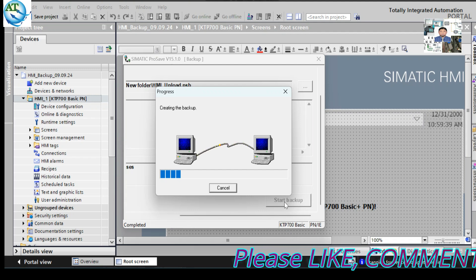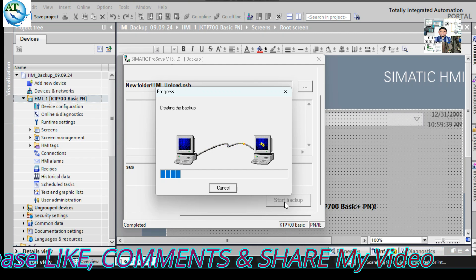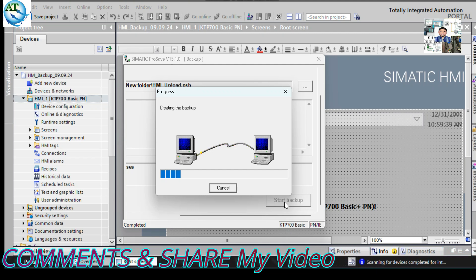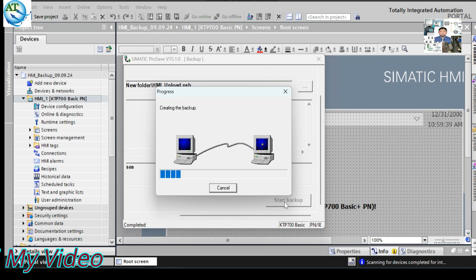In this video, I will show only the backup process. I cannot show you the restore procedure because the machine must be stopped for restoration, but our machine is currently running. The restore procedure is the same: create the project with the same HMI model, go online, select the HMI project, then go to online and HMI maintenance where you will see the 'Restore' option. Select the stored backup program, then press 'Start Restore'. The program will be restored to the HMI. It is very straightforward — same procedure as taking the backup.